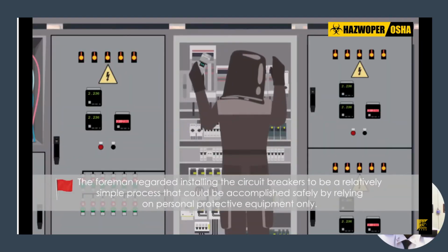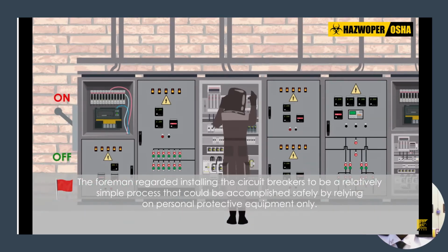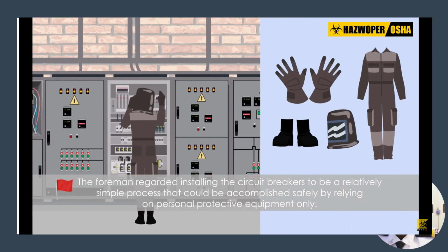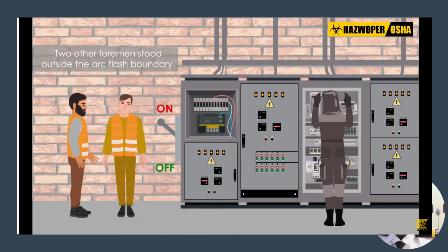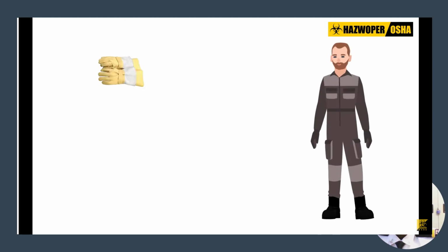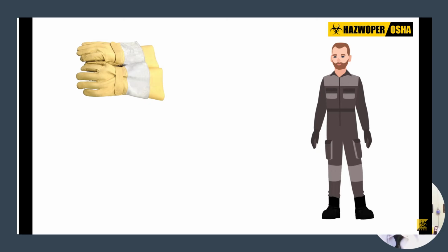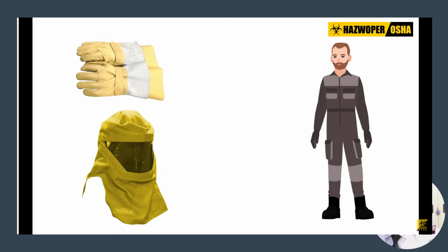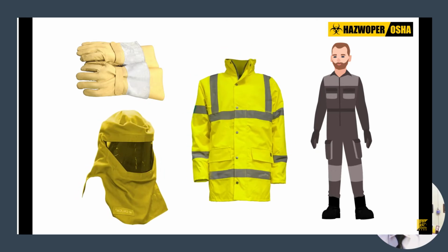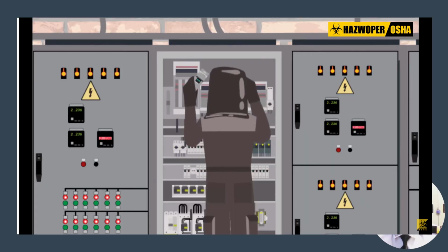The foreman regarded installing the circuit breakers to be a relatively simple process that can be accomplished safely by relying on personal protective equipment only. Two other foremen who were not wearing any personal protective equipment stood about 10 feet from the distribution panel, which is outside the arc flash boundary for that piece of equipment. The victim reportedly wore leather gloves over rubber insulating gloves, arc flash headgear with a face shield, and an arc flash jacket. The foreman uneventfully installed the first circuit breaker.